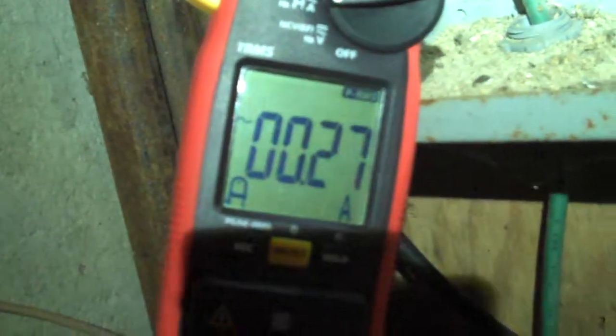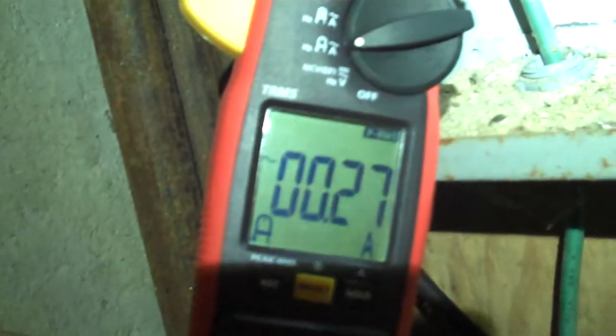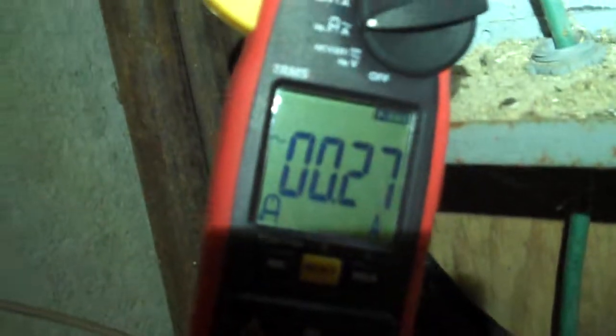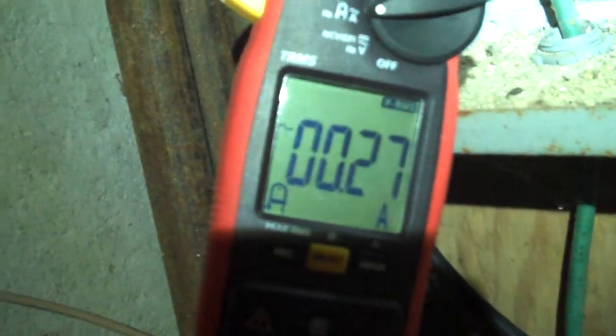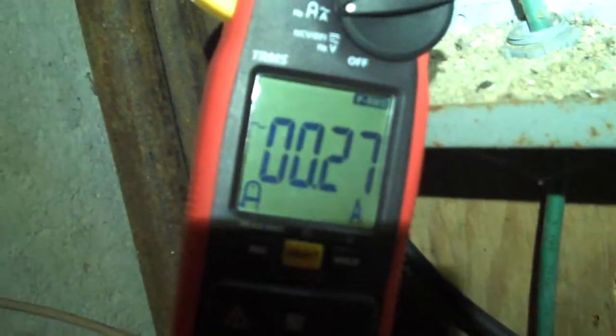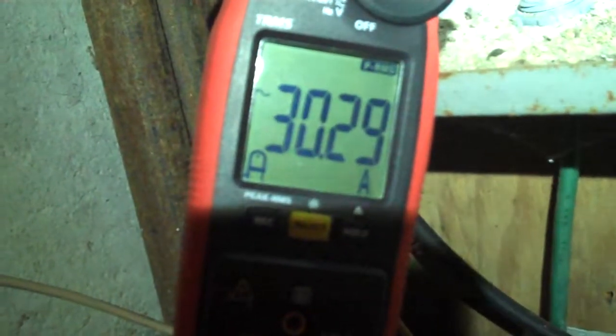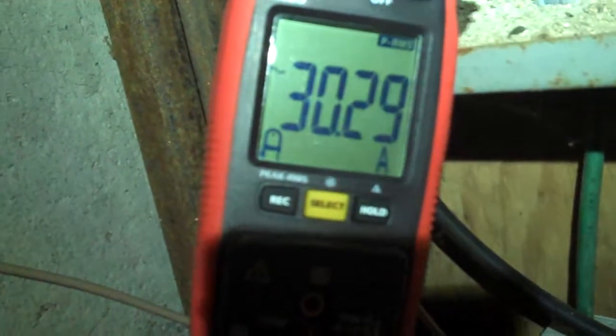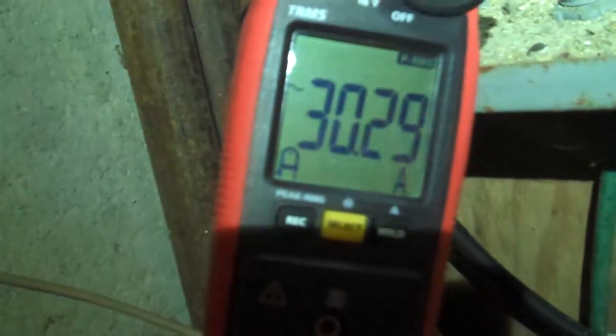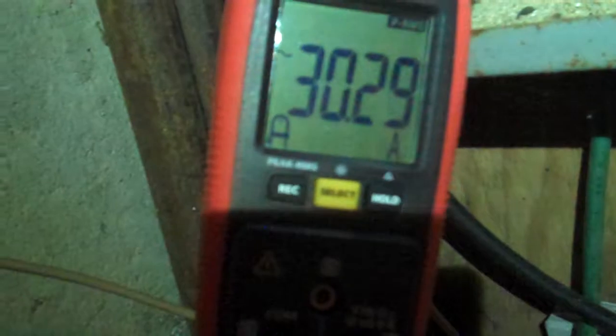So, right now I'm running water upstairs, and you have to run about 8 gallons or so to go from the low level to the high level in the pump, and that will trigger the pump to run. So it could take, there we go, you see that? 30.29 is the measurement I got right there, okay? So that's one leg of power. Okay, turn off the water! Okay, the pump is running. The pump will pump down to the level. That's 30.29.